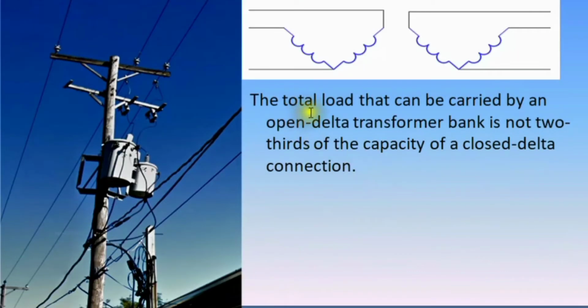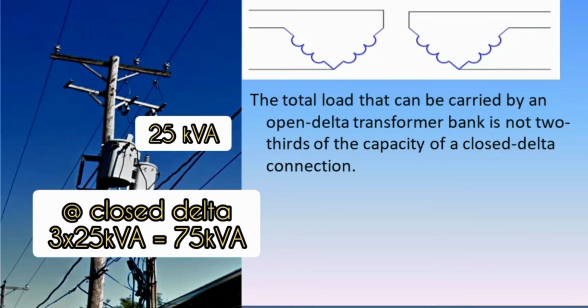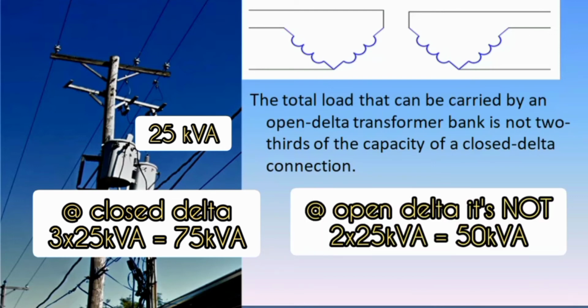The total load that can be carried by an open delta transformer bank is not 2/3 of the capacity of a closed delta connection. For example, if each transformer is rated 25 kVA, at closed delta, the capacity of the bank will give us 3 times 25 kVA, that is 75 kVA. But if open delta is used, then the capacity is not 2 times 25 kVA. It will not give us 50 kVA capacity.